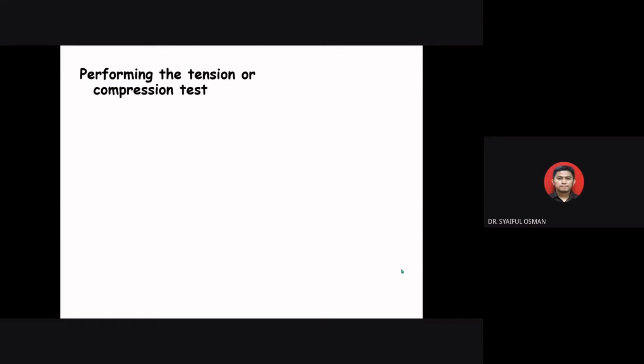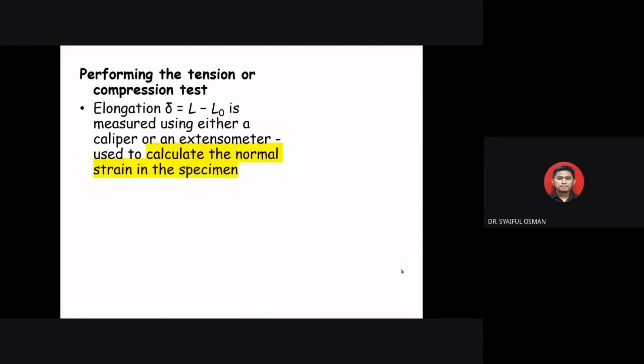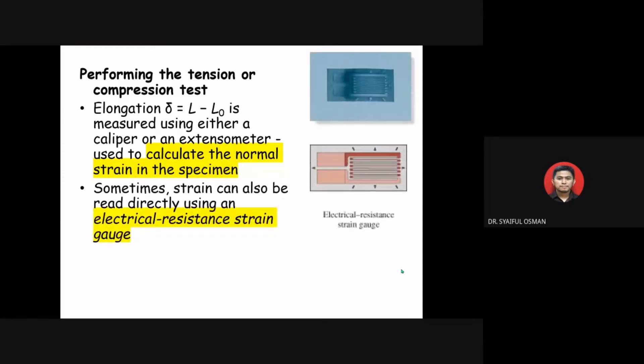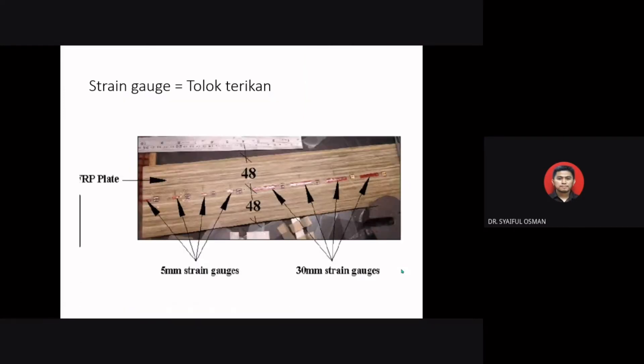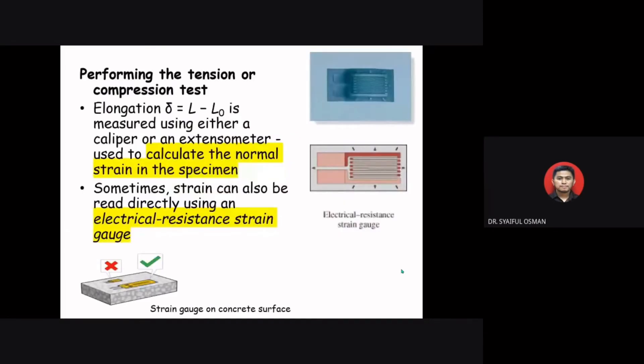To perform tension or compression testing, if we want to determine the elongation, we can use either a caliper or extensometer to calculate the normal strain in the specimen. Sometimes the strain can also be read directly using an electrical strain gauge. The purpose of the strain gauge is to measure the strain or change in length of the specimen — we can stick the strain gauge on the specimen during testing.